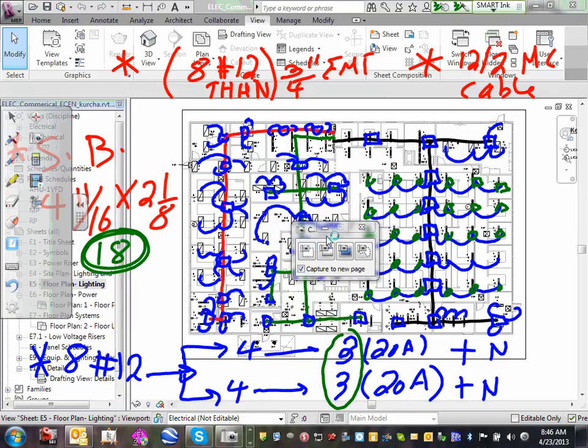You're not worried about blinks and derating and voltage drop? We're using number 12. And we're loading, if you look at, go ahead and look at it. You are inside a small building, guys. You're using number 12. Number 12 can get you 30 amps. When you derate 50% of the 30 amps, what do you get? 15 amps. By code, you can't load it more than 16 anyway.